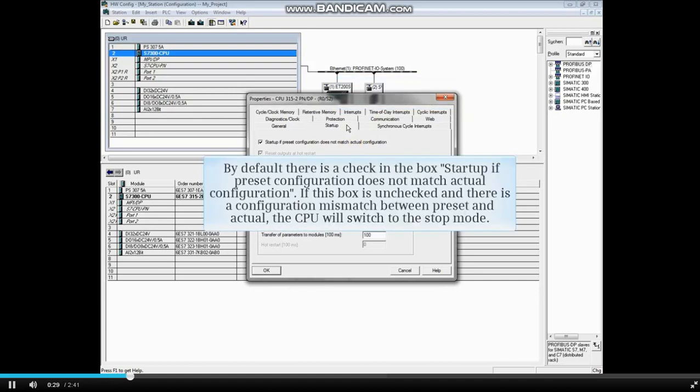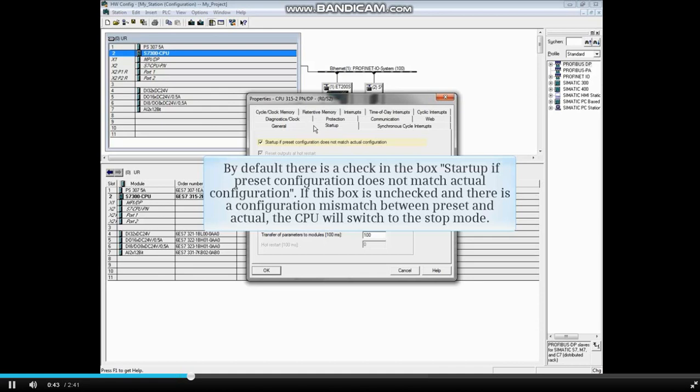By default, there is a check in the box Startup if preset configuration does not match actual configuration. If this box is unchecked, and there is a configuration mismatch between the preset and actual, the CPU will switch to the stop mode.